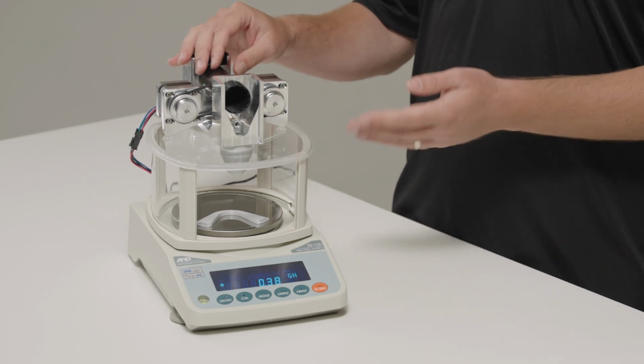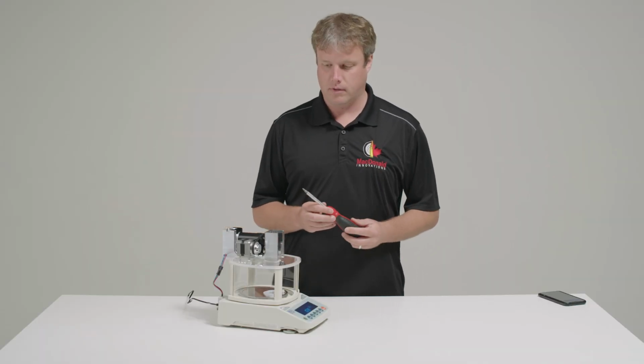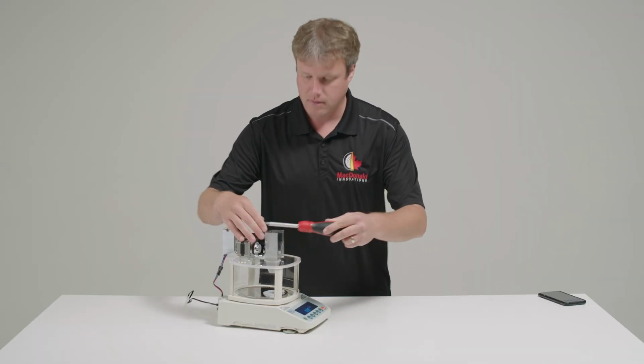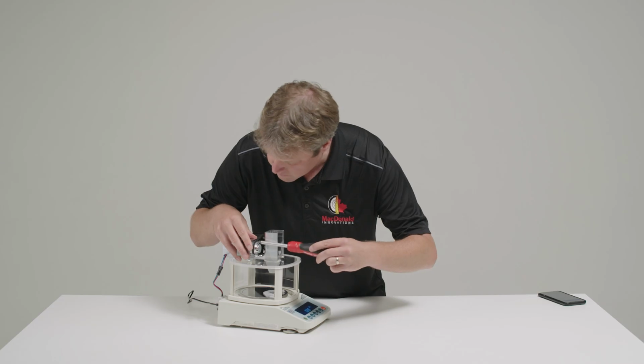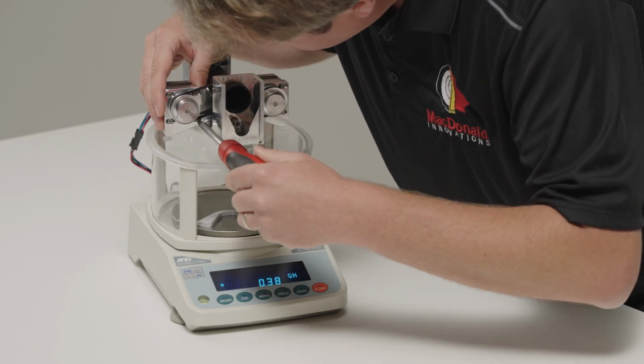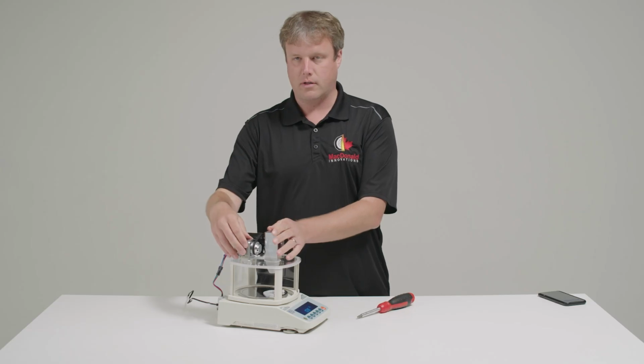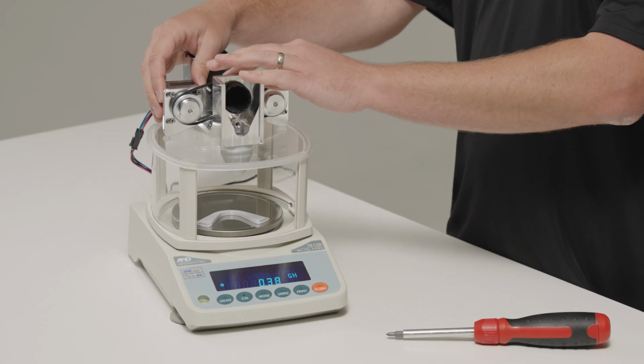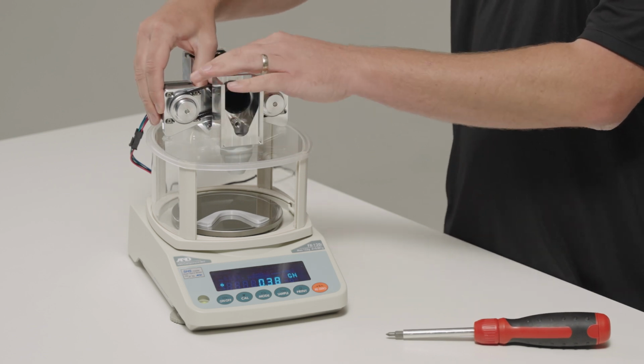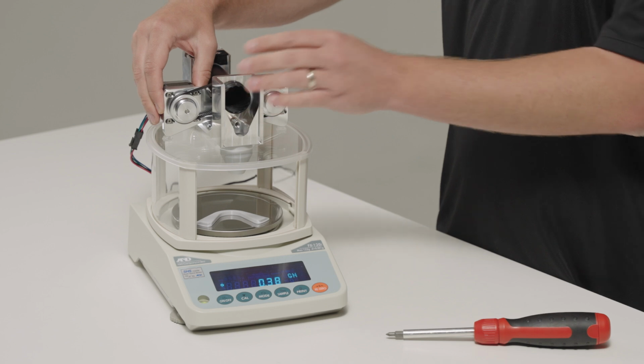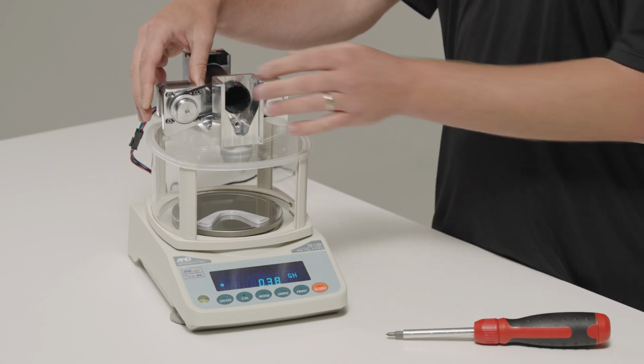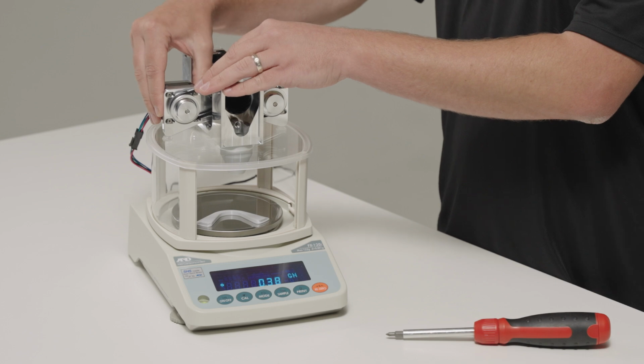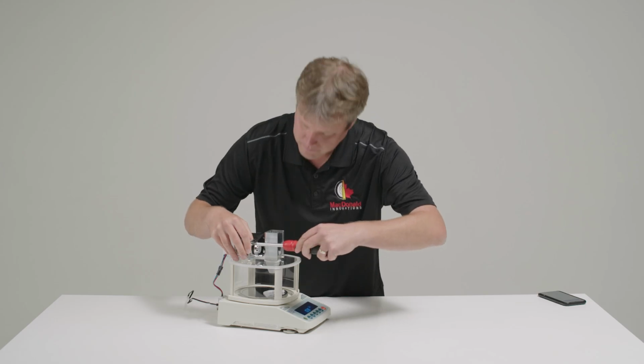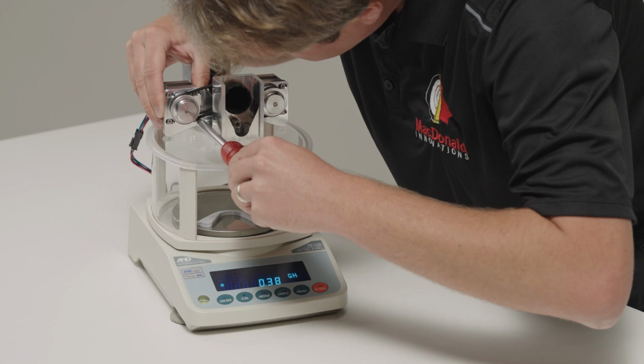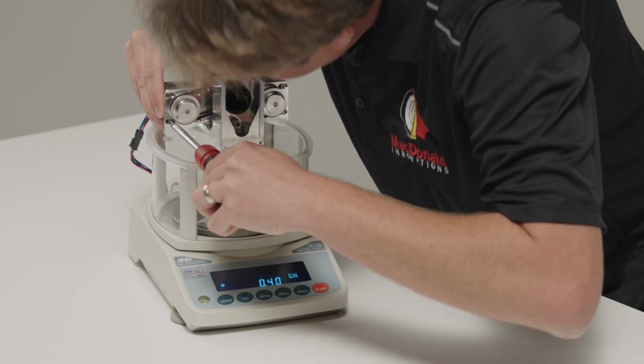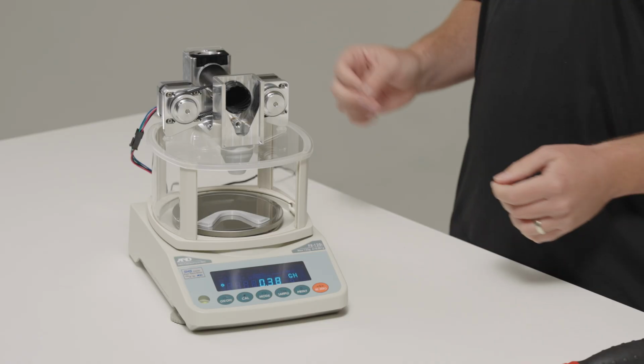So now I'll demonstrate how you can fix this. So we take a Phillips 1 screwdriver, and we're going to be loosening the 4 screws that hold the motor in place. Now with the 4 screws loose, the motor can slide in different positions. So our objective here is to hold the motor so that it's removing the slack from the belt, but not pulling any tighter than it needs to avoid skipping teeth. So just make sure it's not too tight. Looser is always better. And then tighten the screws. Now make sure it can turn freely, and when we run it, it spins normal.